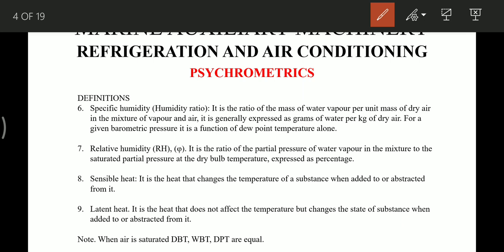The next definition is specific humidity, also called the humidity ratio, which is actually the Y-coordinate of the psychrometric chart. It is the ratio of mass of water vapor per unit mass of dry air in the mixture, generally expressed as grams of water per kg of dry air or kg of water per kg of dry air. For a given barometric pressure, it is a function of dew point temperature alone. Relative humidity is the ratio of partial pressure of water vapor in the mixture to the saturation partial pressure at the dry bulb temperature, expressed as a percentage. Relative humidity is very important for human comfort.